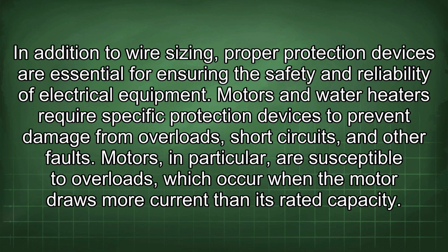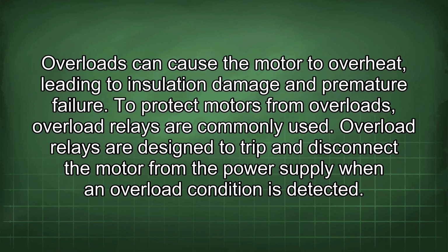In addition to wire sizing, proper protection devices are essential for ensuring the safety and reliability of electrical equipment. Motors and water heaters require specific protection devices to prevent damage from overloads, short circuits, and other faults. Motors, in particular, are susceptible to overloads, which occur when the motor draws more current than its rated capacity. Overloads can cause the motor to overheat, leading to insulation damage and premature failure.